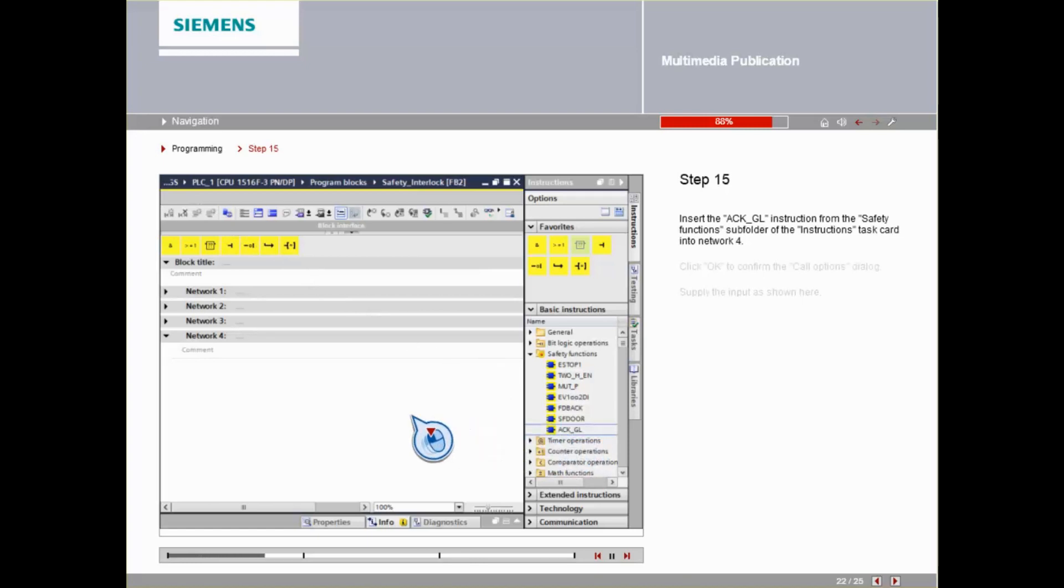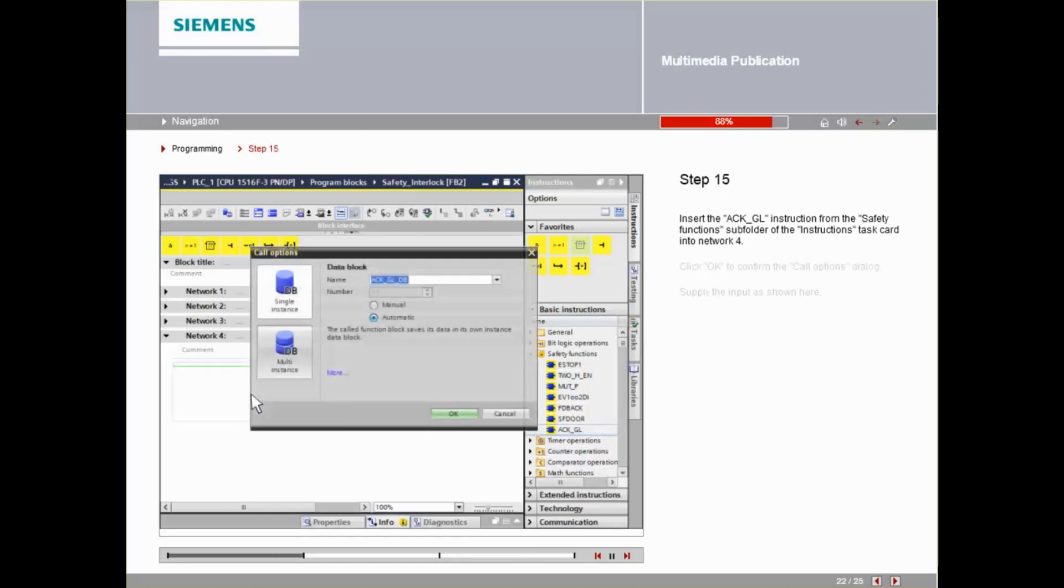Insert the ACKGL instruction into Network 4 from the Safety Functions subfolder of the instructions task card. Click OK to confirm the Call Options dialog. Supply the input as shown here.